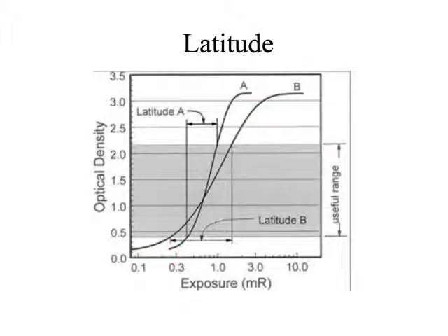That means that these films are made to where they have to get some kind of exposure before they start to do anything. Prior to that, it's just going to be noise, just background. Once it reaches that threshold of exposure, and it's going to be a pretty small threshold, this is a milliroentgen, it's going to start to display optical density.